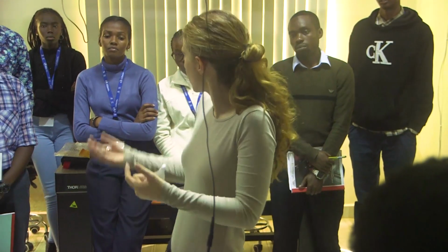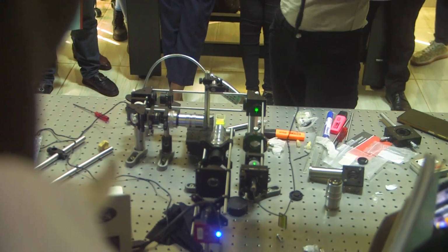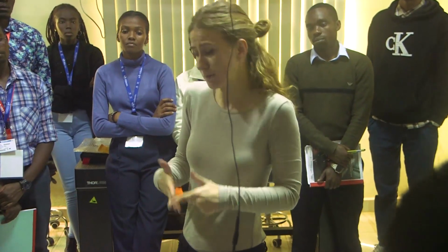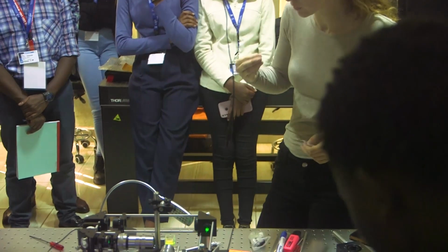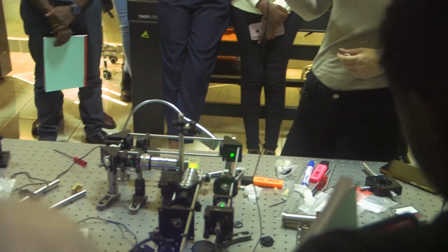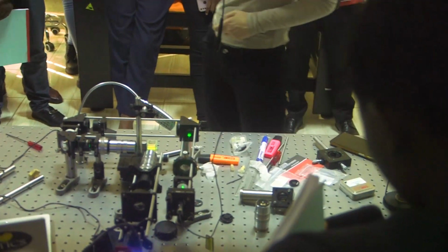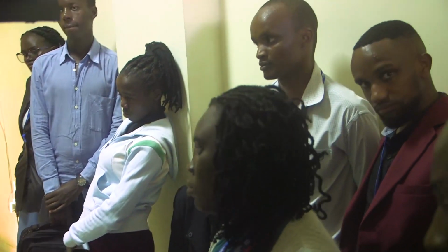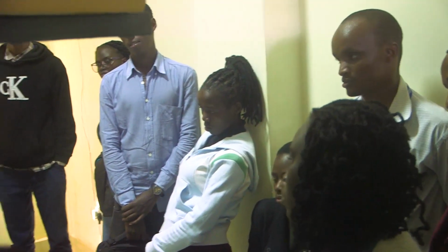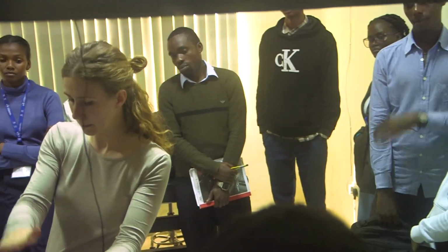So it depends. Sometimes you want a very thin light sheet and a very short Rayleigh length because maybe your sample is small. Other times you prefer to have a longer, let's say, light sheet and a thicker one. But to be able to change that, what can we do? Well, we can start with a very large beam, and indeed that will give us more focusing effect, or we can have a smaller beam, and then the capability of a lens of focusing it will be reduced. So we will have a thicker light sheet and a longer one.